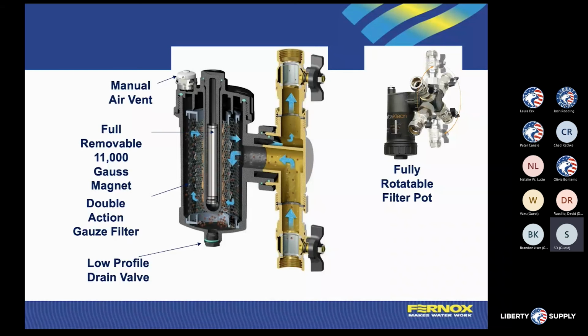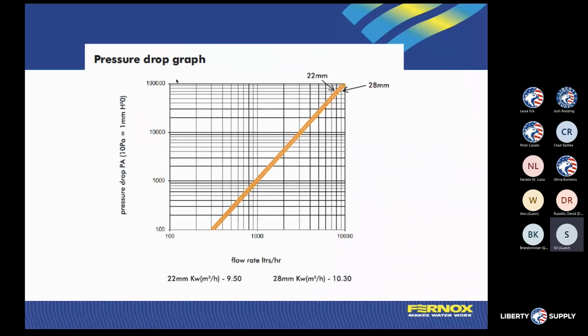Each magnet that's in the system has a different rating. It's going to be rated in Gauss, as you're going to see there. So this particular magnet is at 11,000 Gauss. You'll see ranges from 2,000 or 2,600 Gauss up to 10, 11, 12,000. So that's kind of the range. Typically, a decent magnetic filter should be in that 10 to 12,000 range. It's kind of what we're looking for typically for that system.